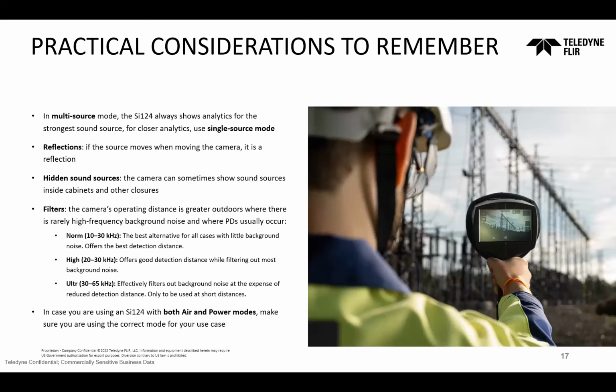This works in a similar way. We have 3 filters. This camera has no auto filtering, so the camera will find the partial discharges in any of the 3 filters, but I recommend you select the one showing a better image of the partial discharge on screen. That will be the one you use to take the snapshots and videos of the partial discharge.